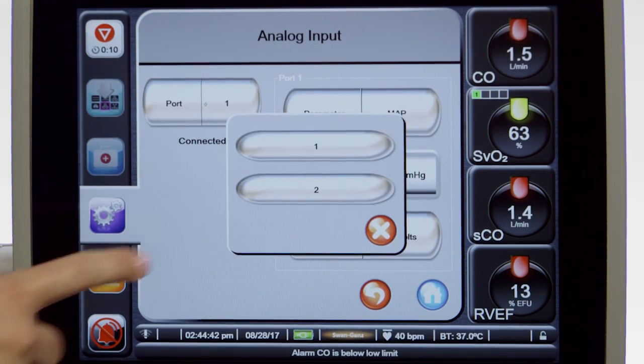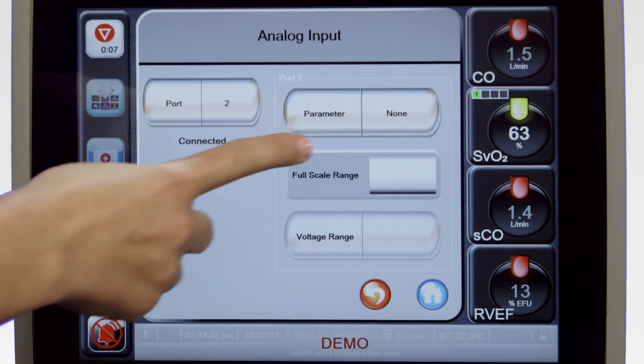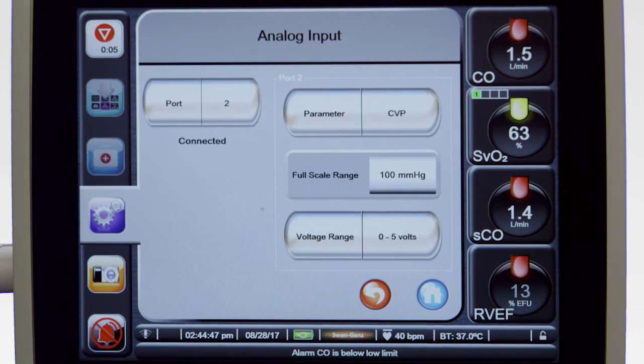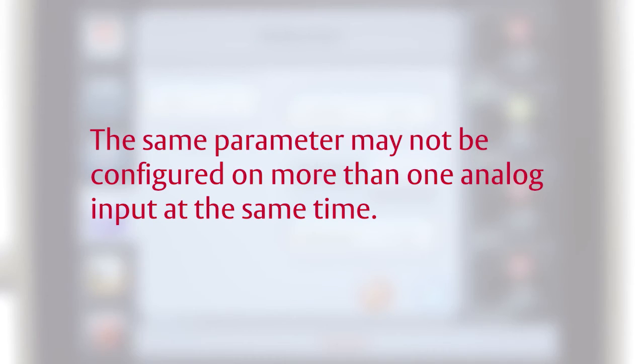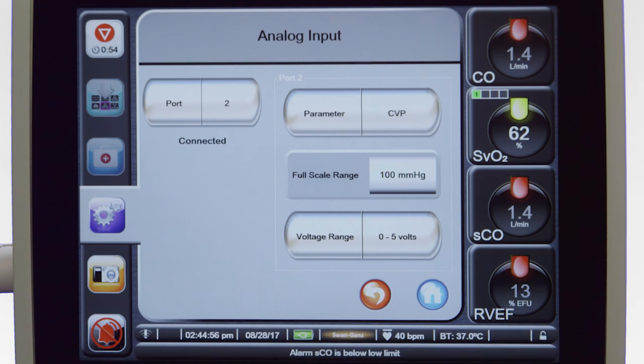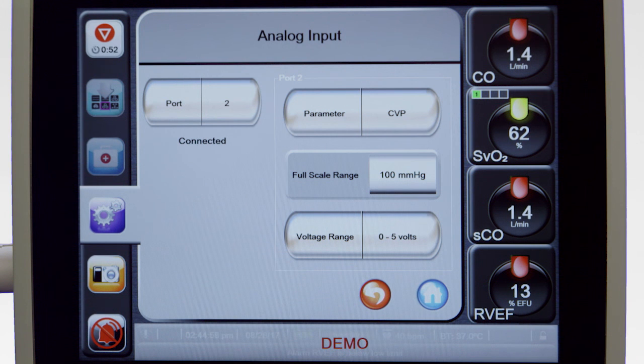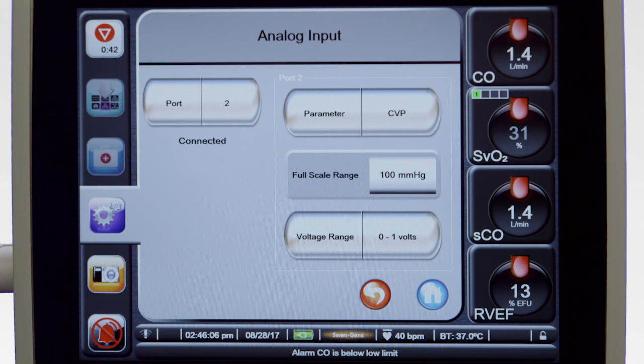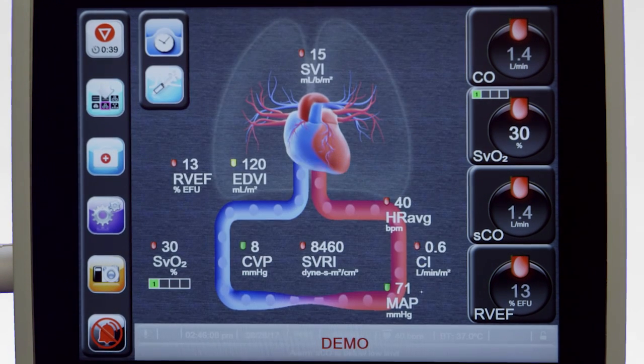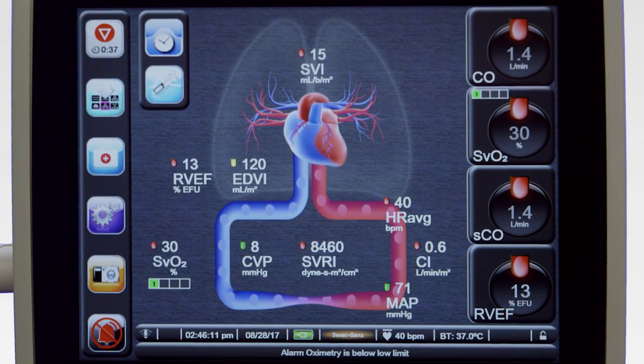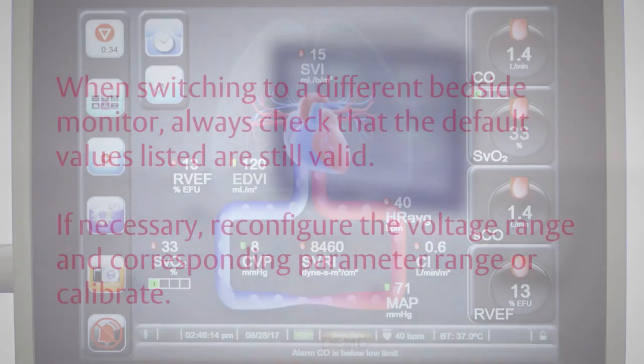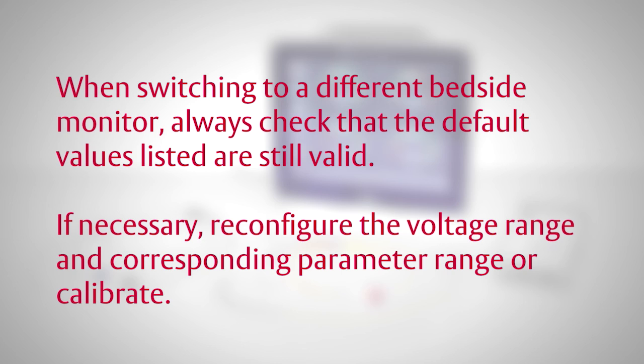Select Analog Port 2. Choose CVP from the parameter list. The default values for CVP will be displayed. The same parameter may not be configured on more than one analog input at the same time. If the default values are correct for the bedside monitor being used, touch the Home button to return to the main screen. The slaved parameters will now be displayed as desired. When switching to a different bedside monitor, always check that the default values listed are still valid. If necessary, reconfigure the voltage range and corresponding parameter range, or calibrate.